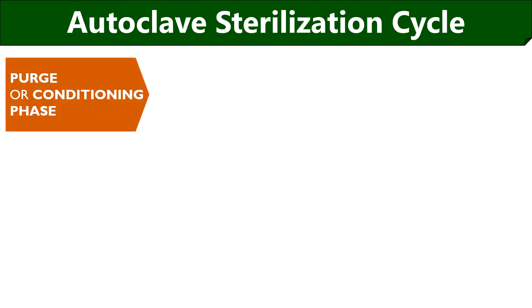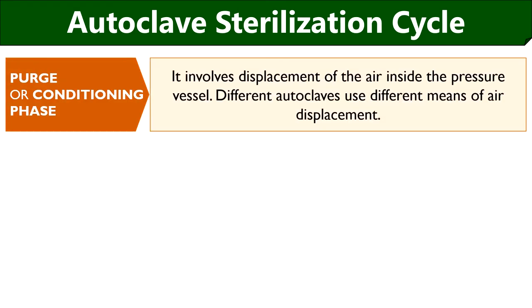Let us discuss the working and stages in the autoclave sterilization cycle. The working of an autoclave is very similar to the ordinary pressure cooker that we use in our daily life to boil or cook food. We can close the lid of an autoclave to form a sealed chamber, and under optimum temperature, pressure and time, the water is converted into steam. Depending upon the working of an autoclave, the sterilization cycle has three consecutive stages. The first one is the purge phase or conditioning phase, which involves displacement of air.